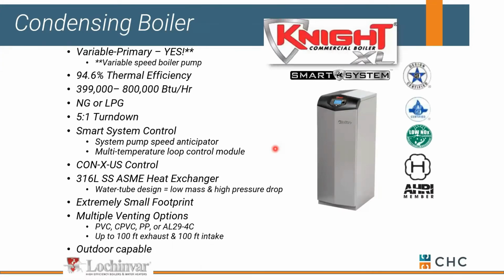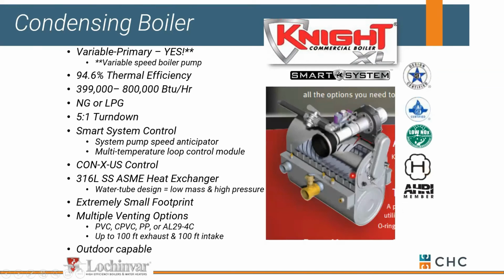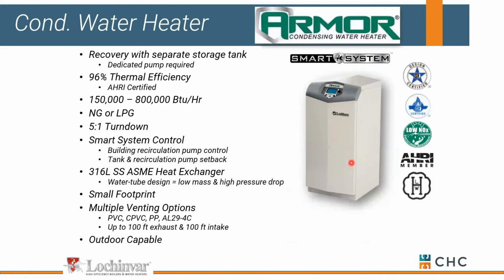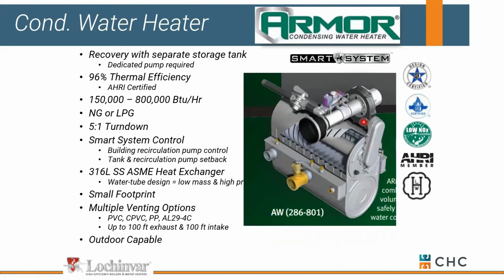Now, manufacturers offer the same product. They sell it one way as a condensing boiler, and they sell it another way as a condensing water heater. So this may not help things. Here we have a gray box set up as a boiler, carries an H stamp. You'll notice that we've got a heat exchanger here with a burner that radiates out. We've got water that flows through the tubes and picks up heat from the burner assembly. Okay, this is set up as a boiler. We go to a light gray box now. Same heat exchanger design, but this is set up as a water heater and carries a different stamping from ASME. You cannot use a water heater to heat a closed loop hydronic system.